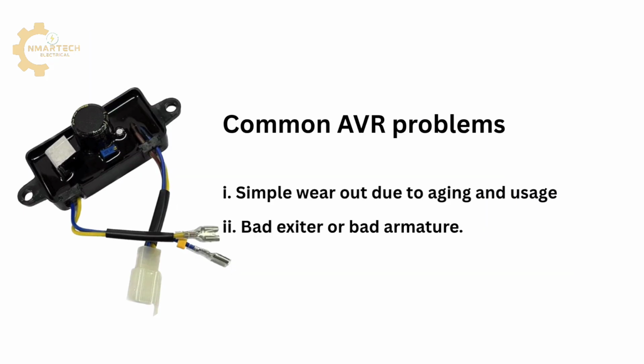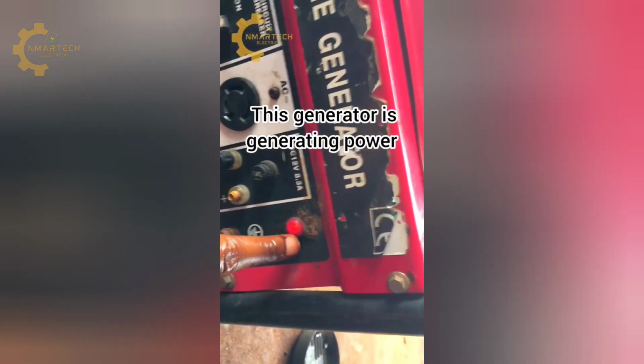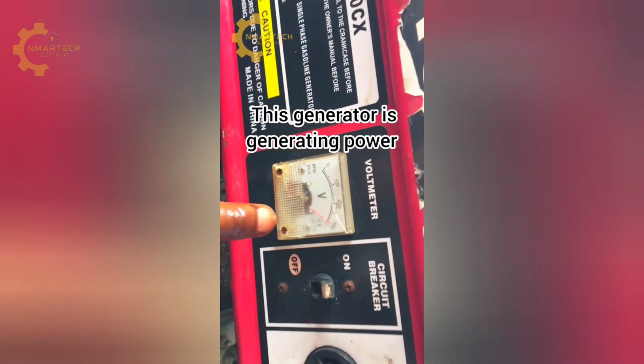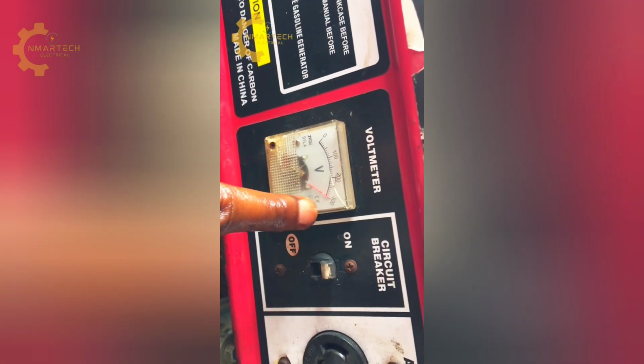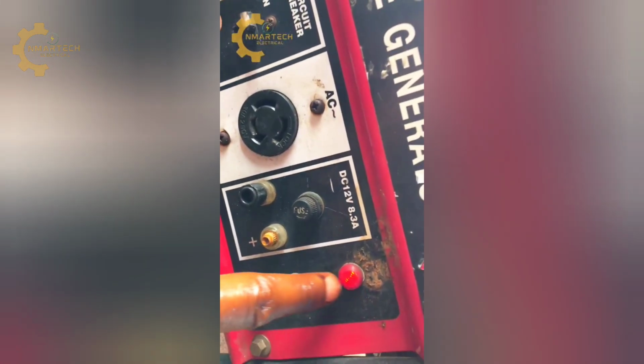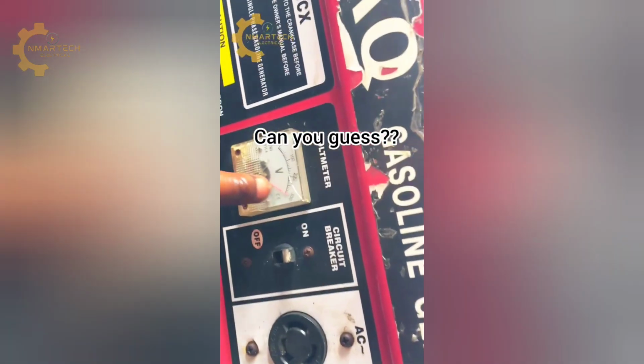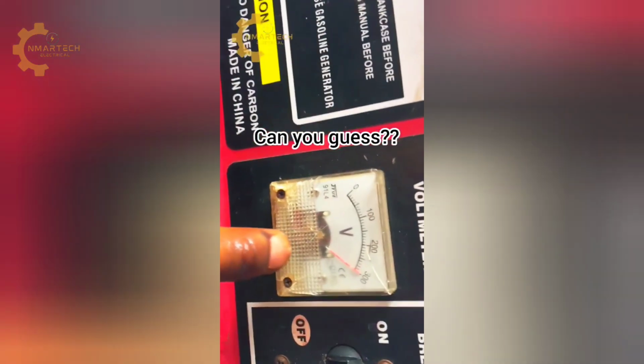Number 2, the AVR can be malfunctioning as a result of a bad exciter or bad armature. In a generator, the exciter coil feeds the AVR while the AVR feeds the armature. Now here is a bonus. Do you know that your generator can be delivering output voltage and yet the AVR is badly damaged? A good example is the gen you are seeing on your screen right now. In fact, this condition is more dangerous than having a no voltage output condition. I'm going to explain later.